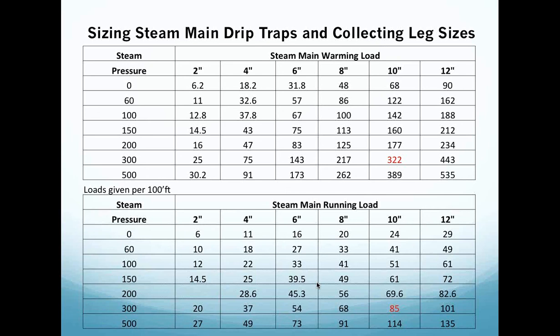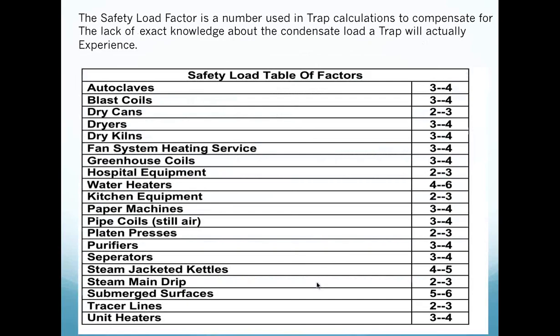And I want you to know this, that in your facilities, when you start your equipment up, there is a much different load on that equipment than when you're at operational processing temperatures. So that's called the running load, and on the warm-up or startup, that's called the warming load or starting load. Okay, so big difference. What we're going to look at now is a safety load factor, and we're going to calculate a couple different applications, and then we're going to apply a safety load factor.